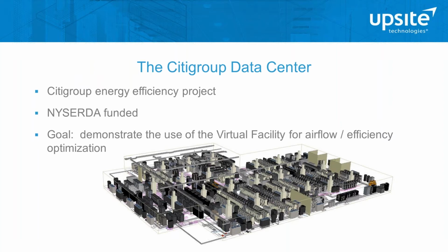78% of the space was used, 53% of the 2.2 megawatts was used, and 100% of the CFM was continuously used for cooling. The PUE was about 1.8, not great but not atypical. Environmental performance was also not great because they had hotspots that concerned them a lot and that they didn't understand.